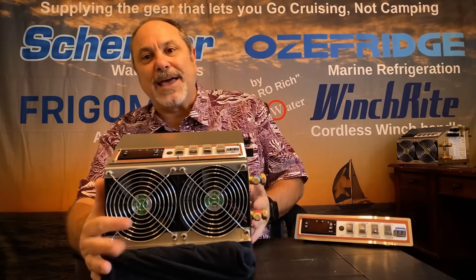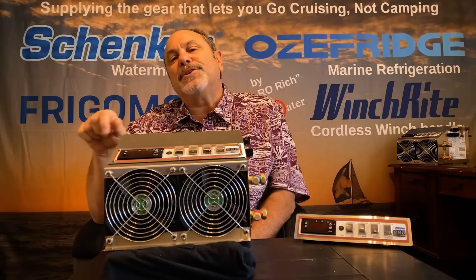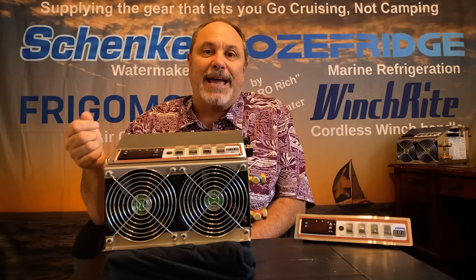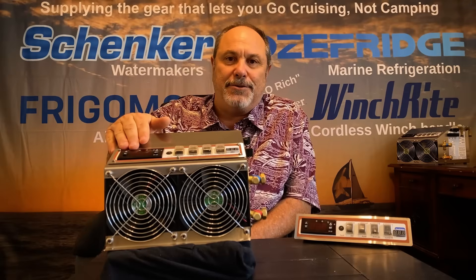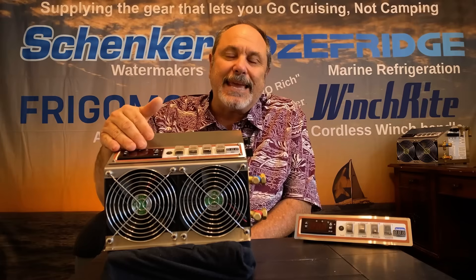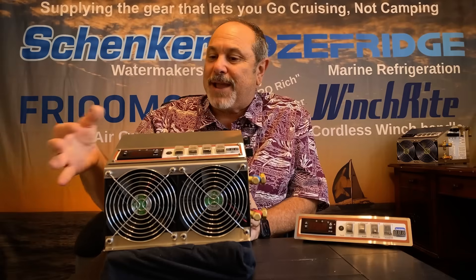Looking at some of the other features, on the front of the compressor unit you'll notice the system controls. Rather than using a one-through-seven rheostat dial that doesn't give you any feedback and precision control, OzeFridge uses a fully programmable digital thermostat unit. You can adjust the display to Fahrenheit or Celsius, visually see what's going on in the unit, and it gives an indication of when the compressor is running in case you can't hear it if it's buried somewhere. It also lets you adjust the cut-in and cut-off temperatures so this compressor unit can operate both a freezer and a refrigerator from the same thermostat.